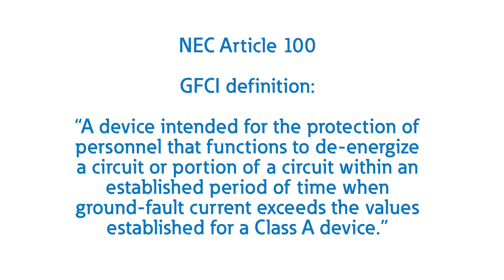We're going to explore this topic as we journey through Section 210.8 for GFCI protection and NEC 2023 changes. To select the right device for any requirement in the code, we leverage defined terms. Remember, this can be a circuit breaker or a receptacle-type GFCI. The definition of a GFCI tells us that when we use the term GFCI anywhere in the NEC, it refers to a device intended for the protection of personnel, functioning to de-energize a circuit or portion of the circuit within an established period of time when that ground-fault current exceeds the values established for a Class A device.